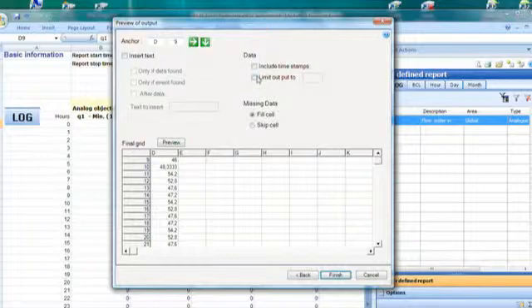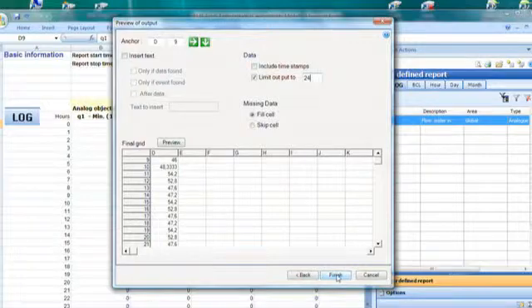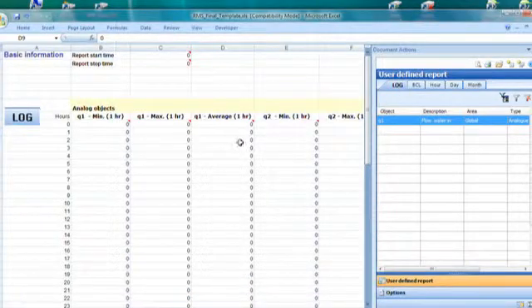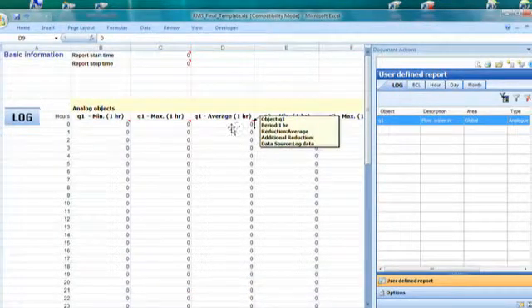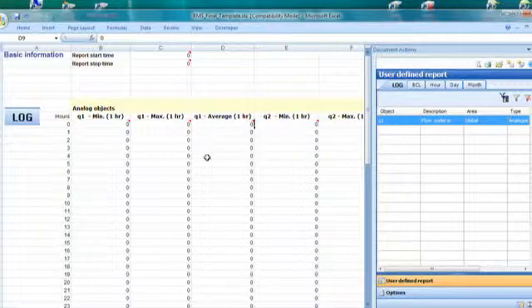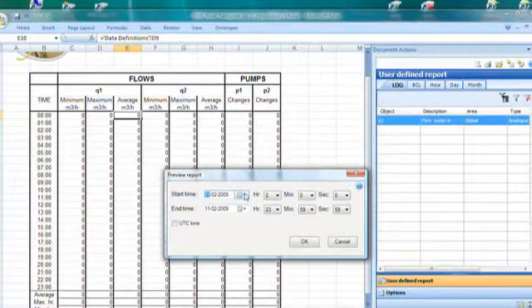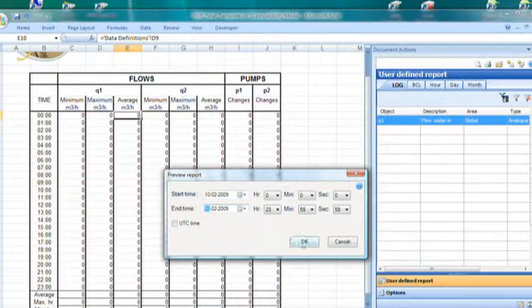You can change the anchor point, of course. In this case, we can limit the output to 24 values, because we only want the 24 hours of the day. Then I click Finish, and I have my final RMS tag indicated by this Excel comment. So when I move back to the log report tab and click the preview button, I will get the 46 value again in that field. So that's how you create an RMS tag in IGSS.